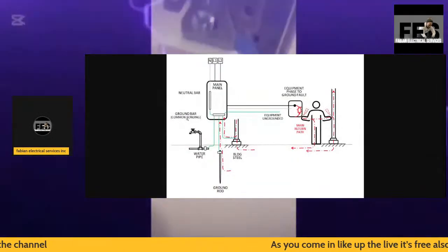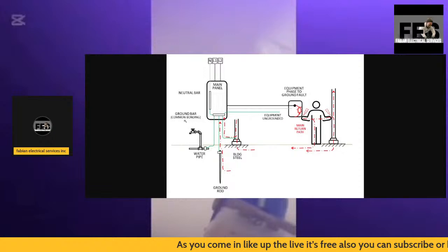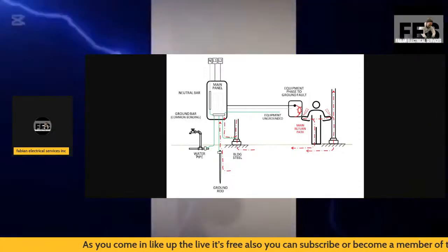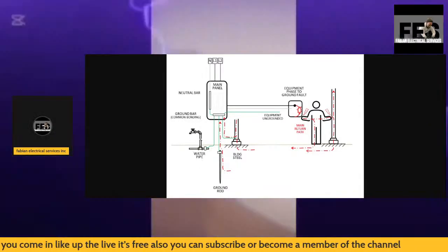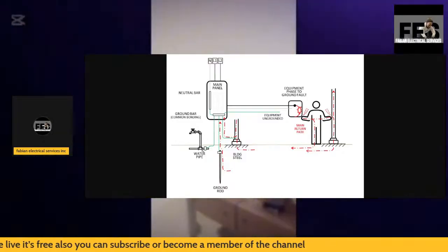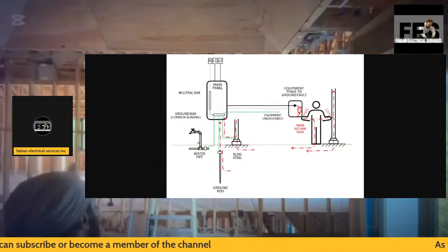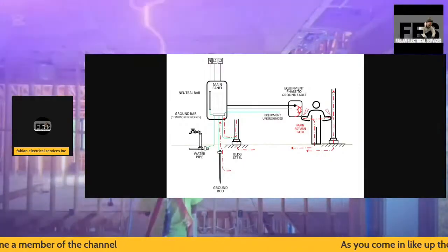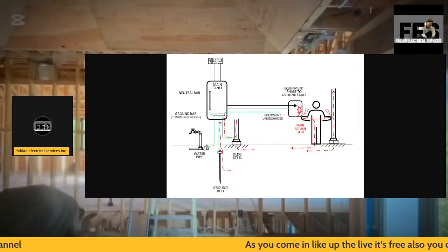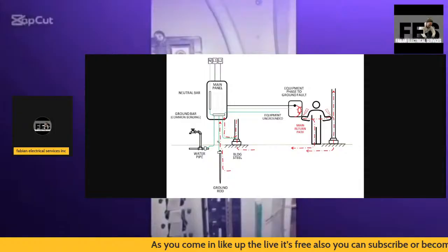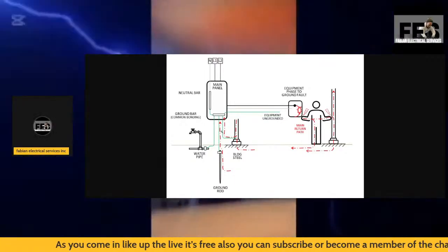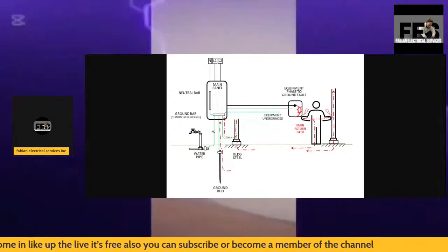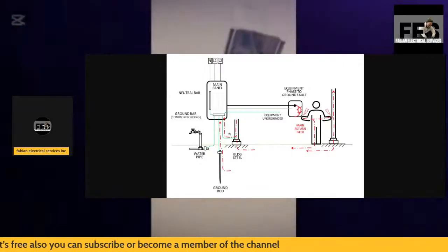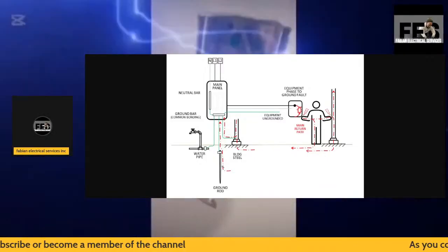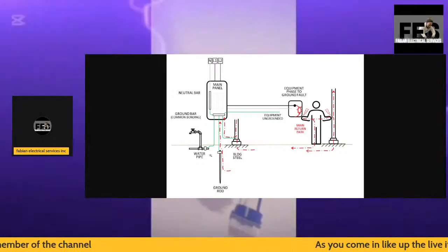So again, here you have your main panel. You have your neutral bar, you have the ground bar, common bonding. You also have your water pipe here - this has to be grounded off your water pipe. Everything going back, of course, is going to be continuous throughout. You have your ground rod here.